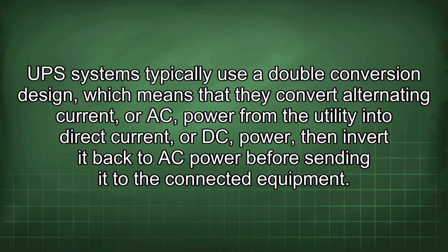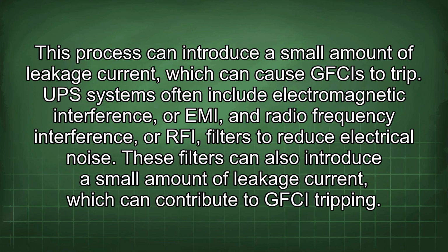UPS systems typically use a double conversion design, which means that they convert alternating current, or AC, power from the utility into direct current, or DC, power, then invert it back to AC power before sending it to the connected equipment. This process can introduce a small amount of leakage current, which can cause GFCIs to trip. UPS systems often include electromagnetic interference, or EMI, and radio frequency interference, or RFI, filters to reduce electrical noise. These filters can also introduce a small amount of leakage current, which can contribute to GFCI tripping.